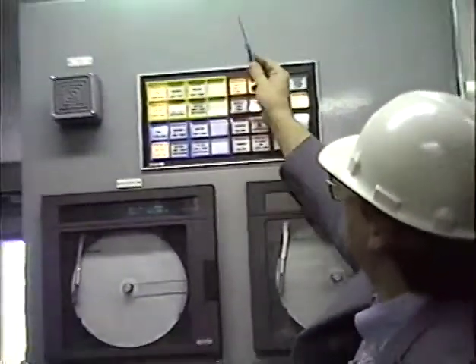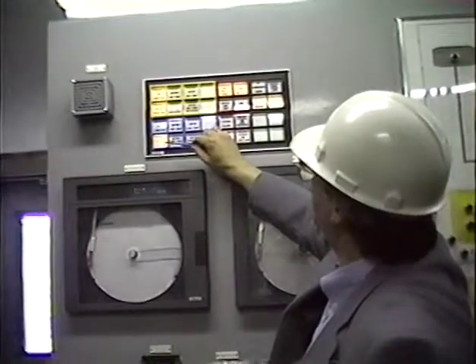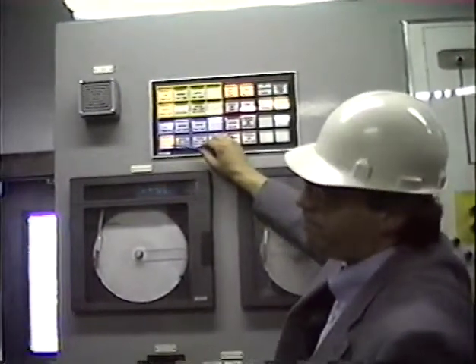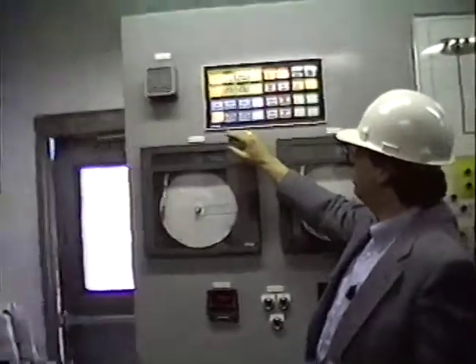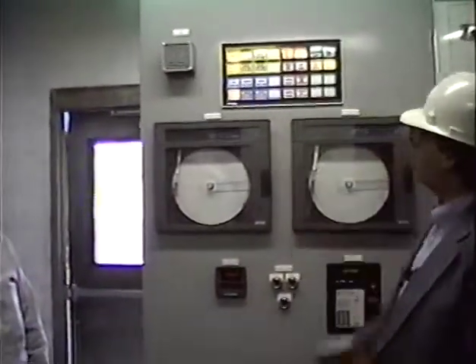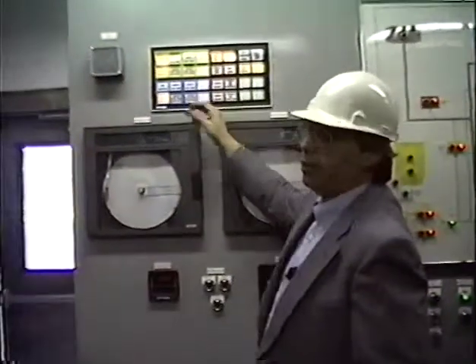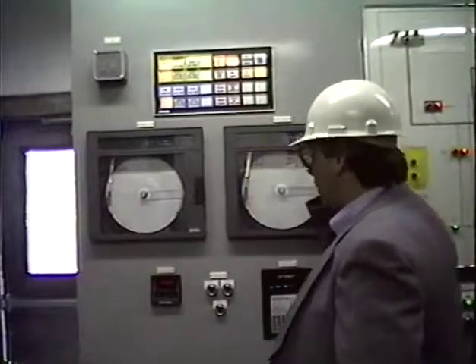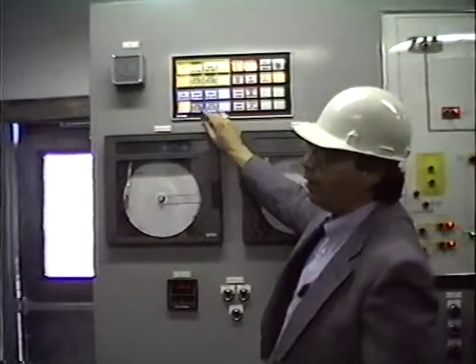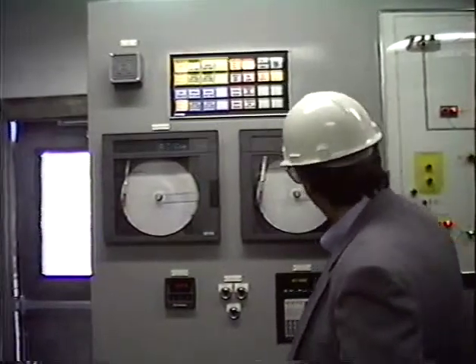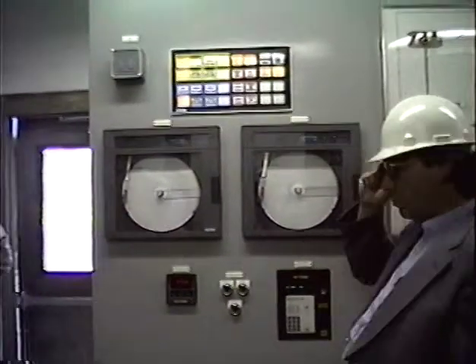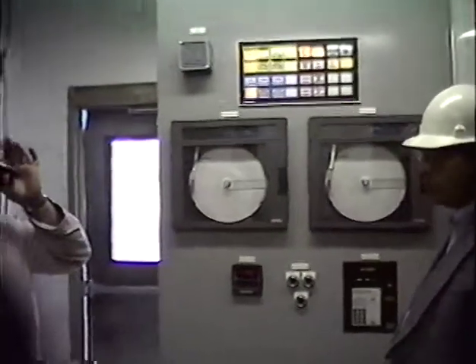Fan one, not operational. Fan two, this is caused by the load track. It's an input from the load track giving us this, and they're in the process of determining exactly what's going on, and they obviously haven't fixed that yet. And this doesn't do anything except receive information and annunciate. They were trying to indicate that this was causing other problems, but that's not the case. Get back into the damper. Well, your damper outside, it regulates automatically as temperature increases. No. When it gets to 250, it goes open. All the way. All the way.